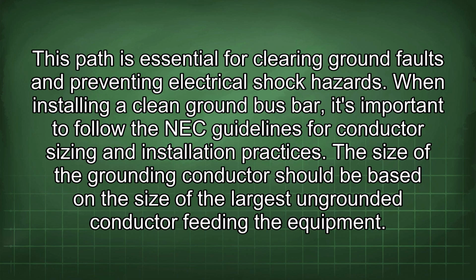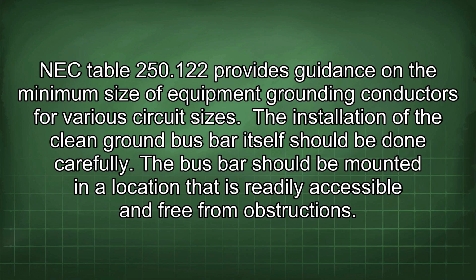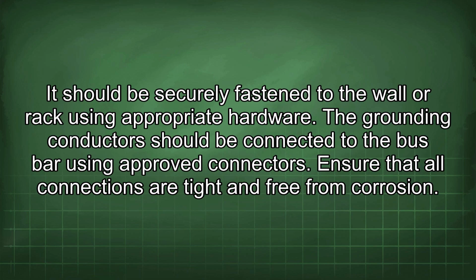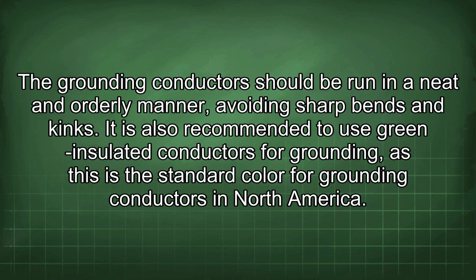When installing a clean ground bus bar, it's important to follow the NEC guidelines for conductor sizing and installation practices. The size of the grounding conductor should be based on the size of the largest ungrounded conductor feeding the equipment. NEC Table 250.122 provides guidance on the minimum size of equipment grounding conductors for various circuit sizes. The installation of the clean ground bus bar itself should be done carefully. The bus bar should be mounted in a location that is readily accessible and free from obstructions. It should be securely fastened to the wall or rack using appropriate hardware. The grounding conductors should be connected to the bus bar using approved connectors. Ensure that all connections are tight and free from corrosion. The grounding conductors should be run in a neat and orderly manner, avoiding sharp bends and kinks.